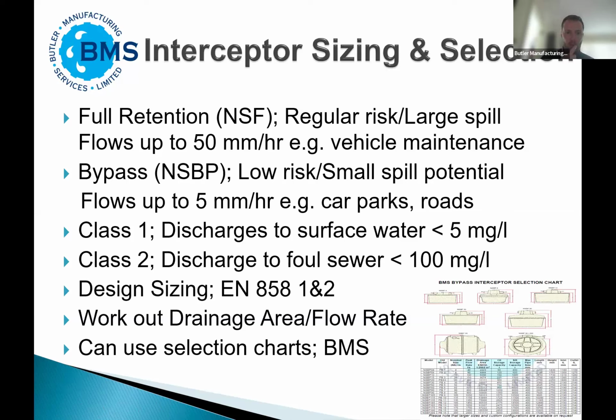And then you'll often hear a class one or class two interceptor. That's simply that a class one discharges surface water and has to have less than 5 milligrams per litre of petrol and oil. And a class two will be suitable for discharge to a foul sewer and has less than 100 milligrams per litre of petrol oil because it's going to a sewer.